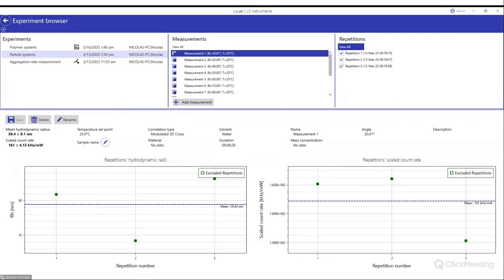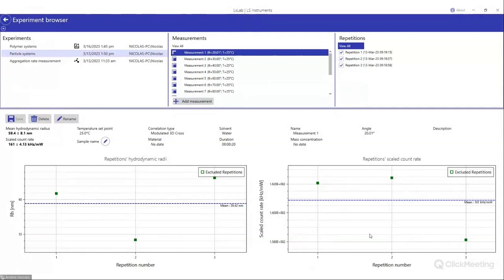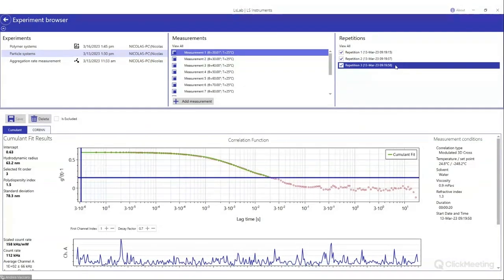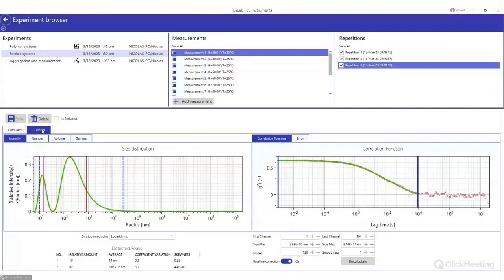This gives more insight because the user can single out outliers and find problematic measurements. Selecting a single repetition, they can analyze the cumulant fit results — seeing the fit range, hydrodynamic radius, polydispersity index, and intercept. For even more detail on the particle size distribution, the CONTIN tool delivers this information. On the left graph we see the particle size distribution, and on the right how good the fit is. CONTIN was able to single out two peaks: a first peak of interest and a second peak likely corresponding to aggregates or contamination.